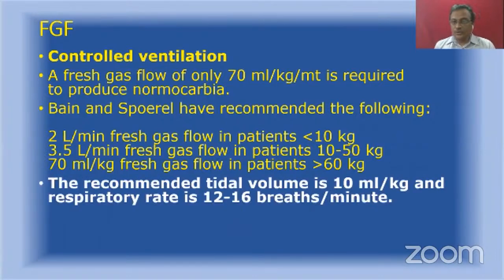And I said it is for controlled ventilation. So whenever you control the ventilation, the tidal volume should be around 10 ml per kilogram and respiratory rate should be around 12 to 16. You should not increase the respiratory rate too much, because if you increase the respiratory rate too much, the expiratory pause will be shortened and there will be inadequate expulsion of the alveolar gas. So that's a very important point. Too much hyperventilation with Bains is not going to do any good for the patient. If you look at the capnogram, you will see that with hyperventilation, the baseline is simply increasing. So the maximum rate of 12 to 16 is ideal. Never go more than that.